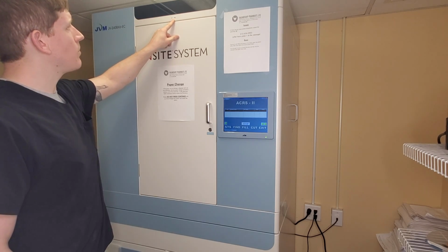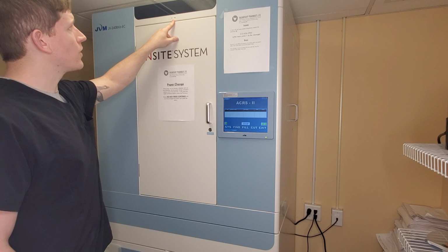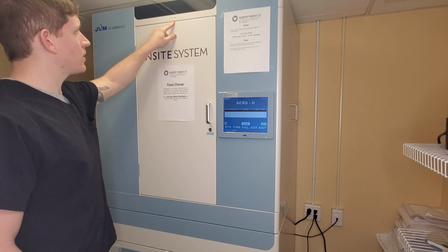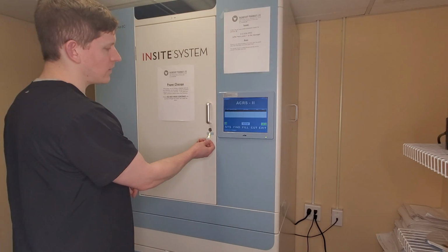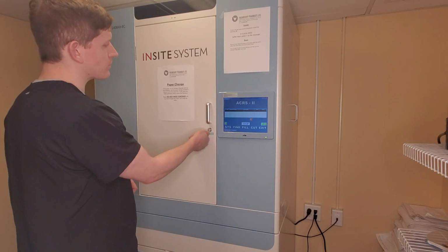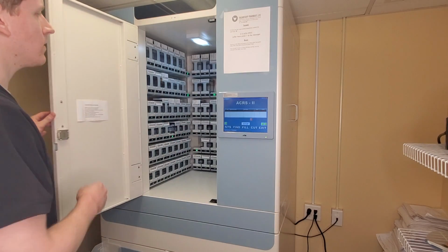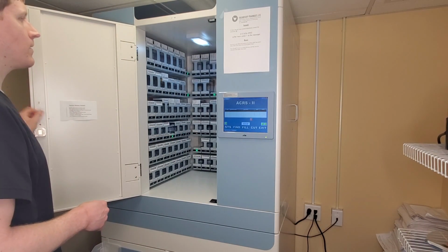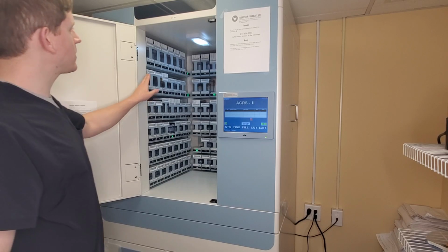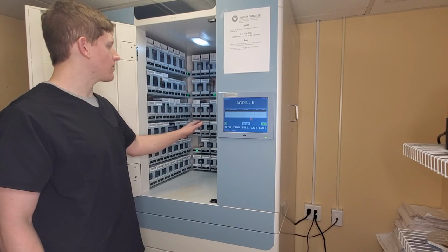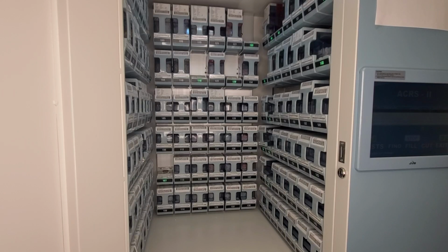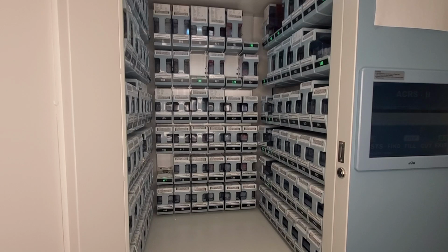Once you open the door, you will see that the canisters are numbered descending, and then at the top right corner it begins again. That's how we can find the canister that we need to fix. In this next clip, I will show you how to unjam the canister or fix it if it was jammed. In this instance, my canister that is troubling me is 178.